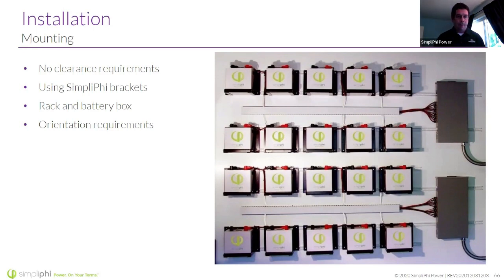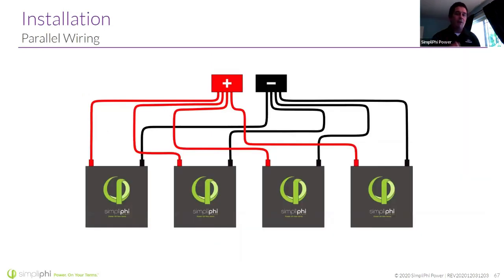We are going to wire all of our batteries in parallel. There will be no daisy chaining and no series of our batteries. So in this example, the red cable that goes directly here is the same length as this red cable that snakes all over the place. We have equal length battery cables to either our common DC combiner or our inverter terminals.